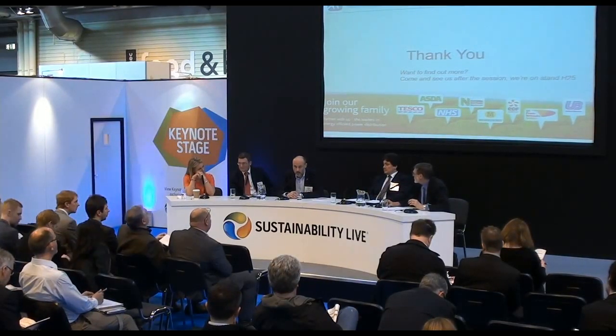Yeah, that's absolutely true. We always recommend that you do a wind assessment, and what we're looking at is the wind speed at the hub height, which is critical, and we're also looking at turbulence and wind shear, which is the difference in the force between the top of the blade at the top of its rotation and the blade at the bottom of its rotation. And different turbines are designed to different wind classes, different design standards. So you should always check that the machine that you're putting in is the right machine for the regime it's going into. And usually it's the turbulence and the shear where you lose power, and you do need to allow for that. And in some cases, we have had one case recently where we recommended that you don't install a wind turbine because those forces were too high.